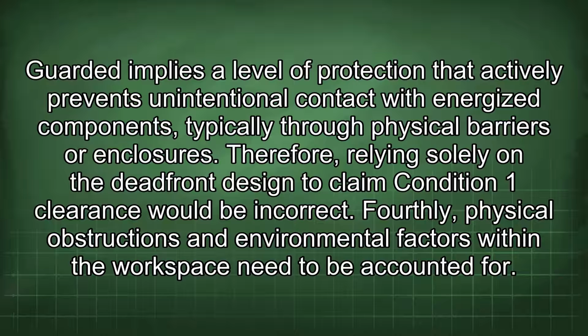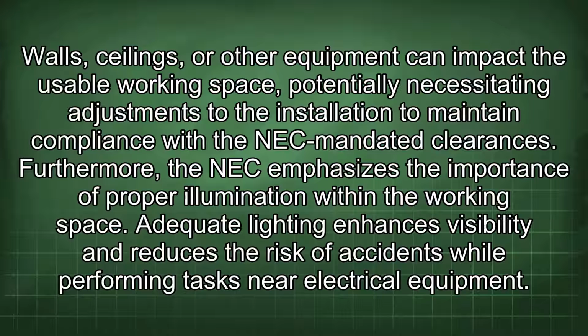Fourthly, physical obstructions and environmental factors within the workspace need to be accounted for. Walls, ceilings, or other equipment can impact the usable working space, potentially necessitating adjustments to the installation to maintain compliance with the NEC mandated clearances. Furthermore, the NEC emphasizes the importance of proper illumination within the working space. Adequate lighting enhances visibility and reduces the risk of accidents while performing tasks near electrical equipment.